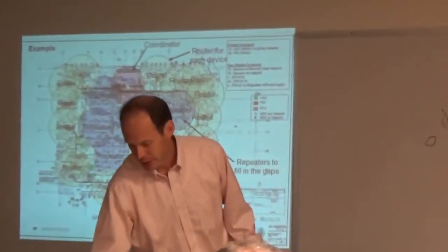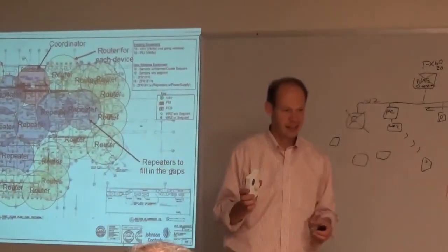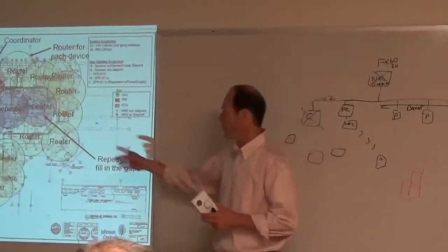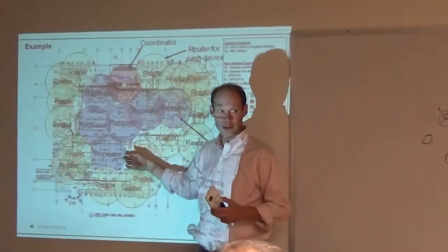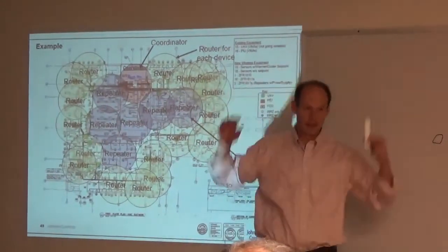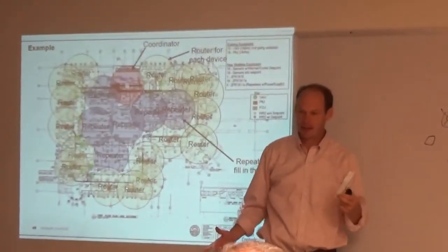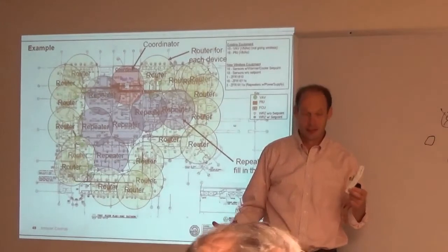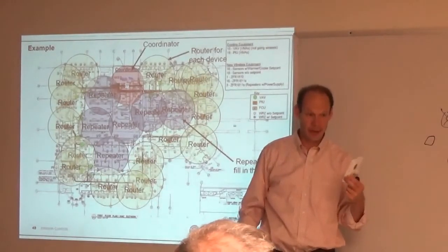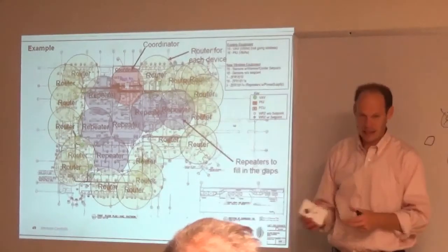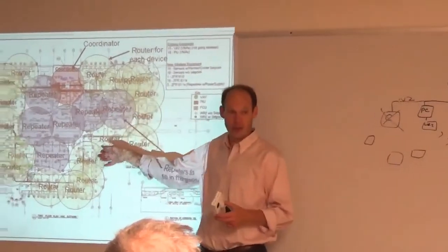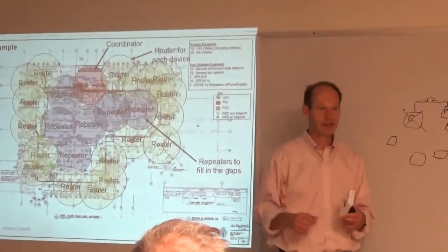One of the big problems people have on their first wireless jobs is they turn the stats on, and they have no coordinator or controller to talk to. So the thing is constantly going, hey, I'm 72, hey, I'm 72, and then it runs out of batteries in about 3 months, because it's on all the time. The key is to keep the stats off. Once you have your coordinator and your controllers up, then power the stats on. You can mount them, just don't power them on.